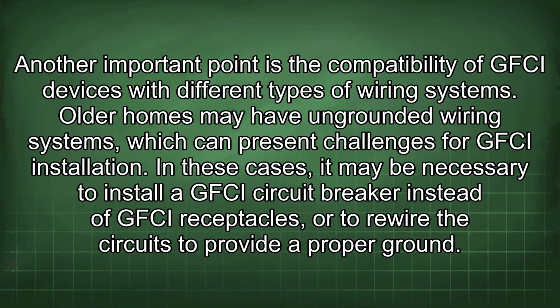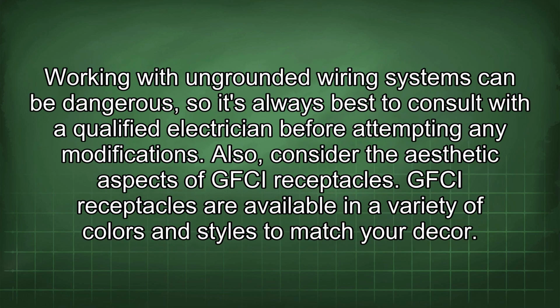Another important point is the compatibility of GFCI devices with different types of wiring systems. Older homes may have ungrounded wiring systems, which can present challenges for GFCI installation. In these cases, it may be necessary to install a GFCI circuit breaker instead of GFCI receptacles or to rewire the circuits to provide a proper ground. Working with ungrounded wiring systems can be dangerous, so it's always best to consult with a qualified electrician before attempting any modifications.